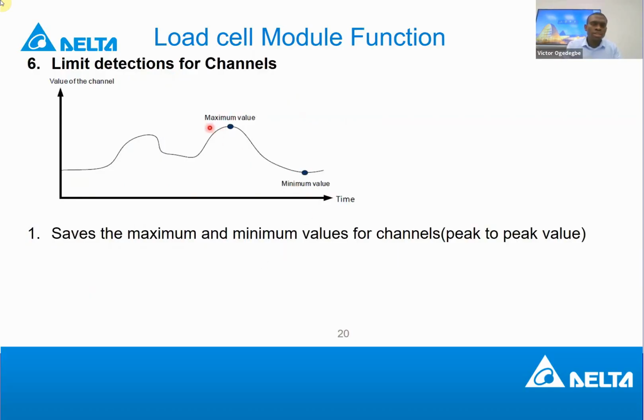That's the fifth. The sixth function is limit detection for channels. It's possible to save the maximum and minimum value for channels, peak to peak. So you can recall what was the maximum value that was measured and what was the minimum. For example, maybe you are working on a machine like a conveyor belt, where the weight is there. Every device is passing and the module is measuring different measurements. Among all the measurements that were made, you can recall what the maximum value and the minimum value were. This is the limit detection function for the channel.